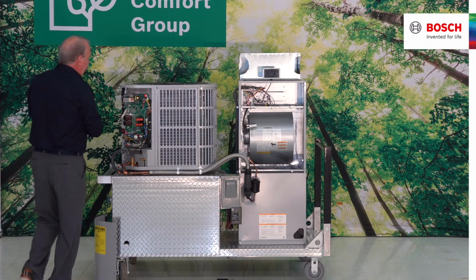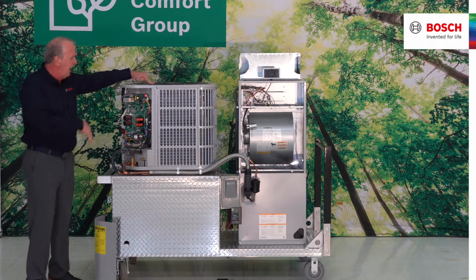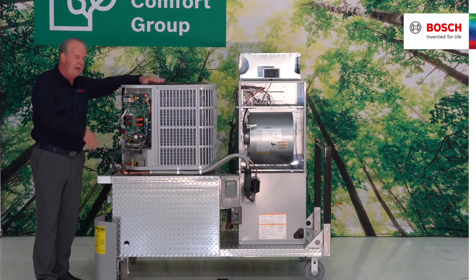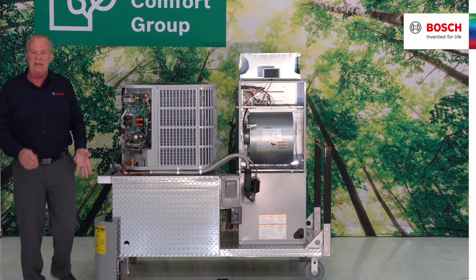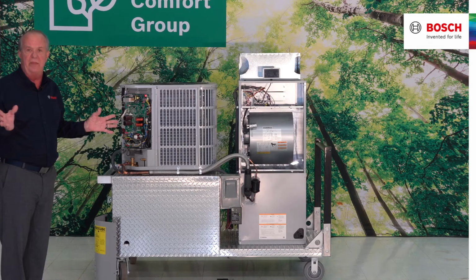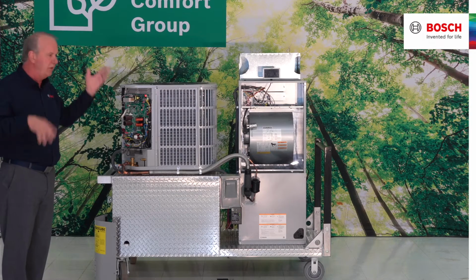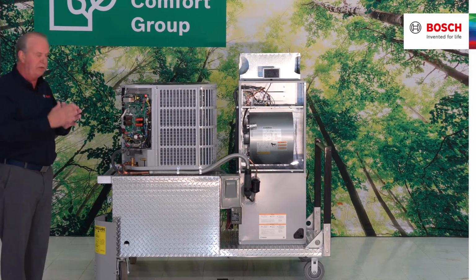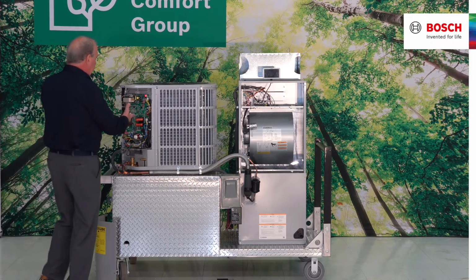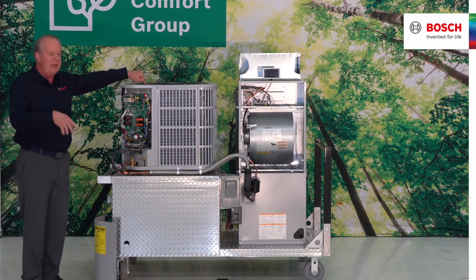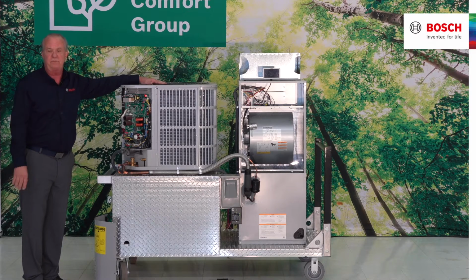And the reason I say leave all of those expensive tools in the truck is because I can get my voltages here, my L1, my L2. I can get my compressor amp draw here. I can get my DC voltage on U, V, and W that goes to the compressor. I can get high side and low side pressures without having to hook any gauges up to it. And I can also read all of my thermistors that are throughout the system: my T1, T2, T3, T5, TF, all the different sensors that communicate back to this board to make it perform in the manner that it does.